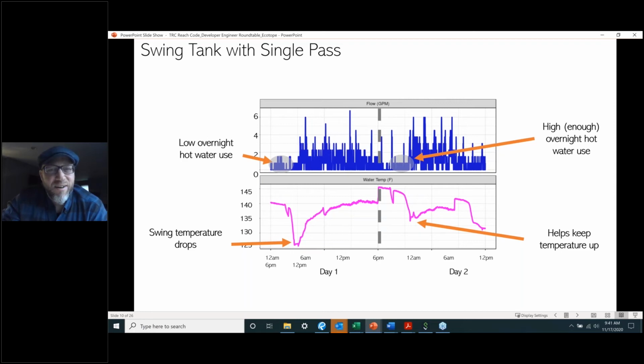So the swing tank with the single pass concept - this is data from one of our projects called Elizabeth James, a 60-unit low-income apartment. We can see the flow data for 2 days. This shows your primary storage feeding into the swing tank, and the bottom shows the temperature of the swing tank. During low overnight use, you're bringing hotter water that trickles through that final swing tank, and it'll essentially heat the recirculation load on its own. So it's a concept that works well.